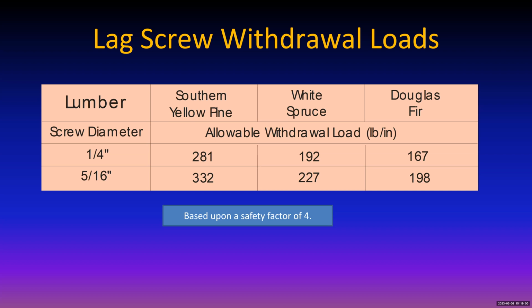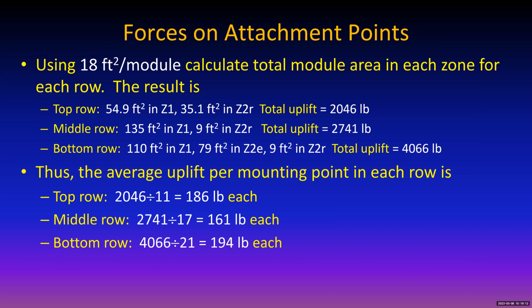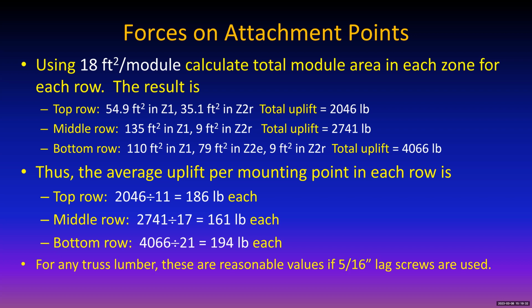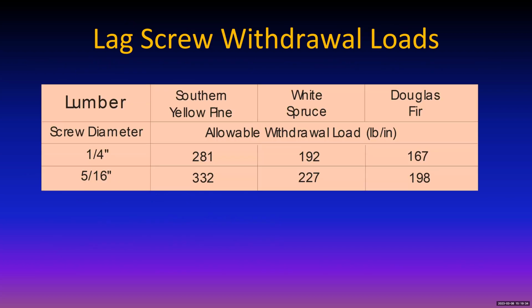How strange. Well, in any case, given the pull strength of 332 pounds per inch, we can go backwards and see here that if we've got lag screws embedded 1 inch, it will hold every one of these attachment points on every row, because the 332 pounds is more than 194, 161, or 186. So I don't need that other row there. We'll go back here now.